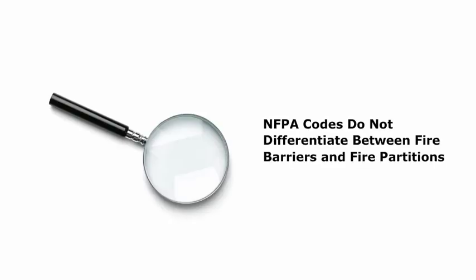The NFPA codes do not differentiate between fire barriers and fire partitions. However, by allowing exceptions to the requirements for fire barriers in cases where the IBC calls for fire partitions, and by adding requirements where a higher level of separation is necessary, the fire rating requirements of the codes are similar.